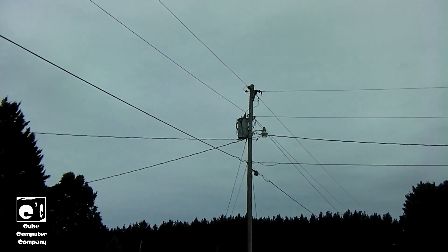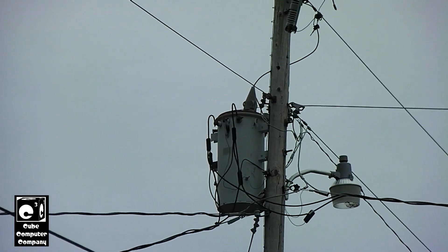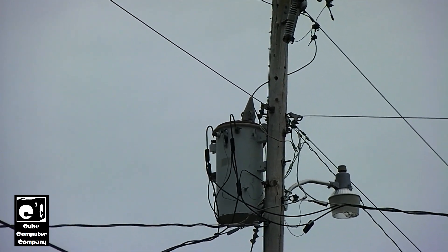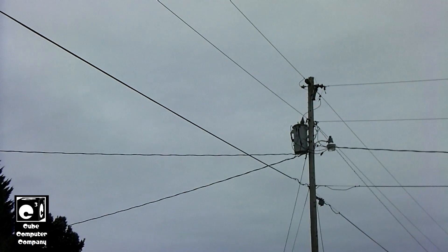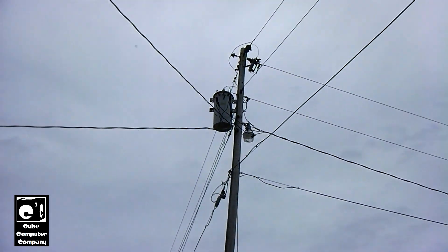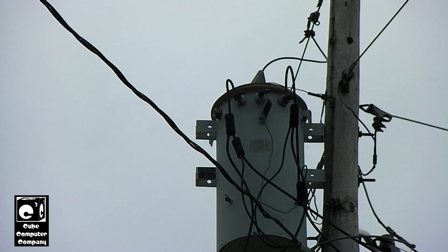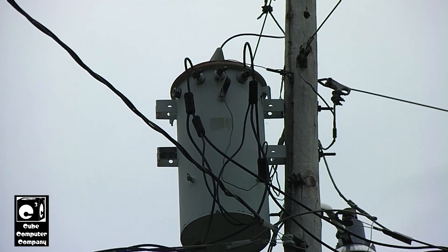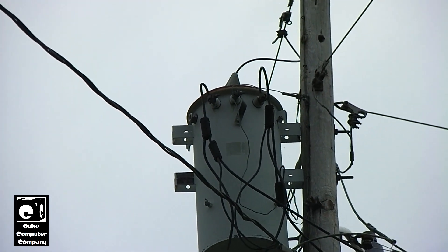I figured I'd take this opportunity, since the last video has really gained some traction on YouTube, to talk about transformers. That out there is a 50kVA General Electric transformer from 1984, and we're looking at the side where the secondary taps come out. This is called a completely self-protected transformer. Right on the side of the transformer, to the left of the secondary taps, there is a handle — that is a breaker. The breaker operates on overcurrent, but it also detects over-temperature in the transformer. These transformers are oil-filled, and if the transformer gets too hot, it will trip the breaker.